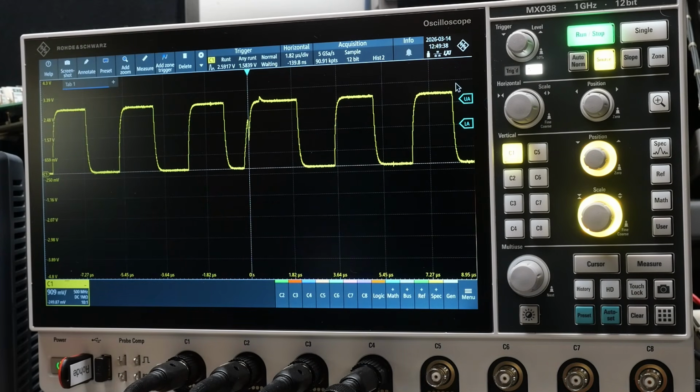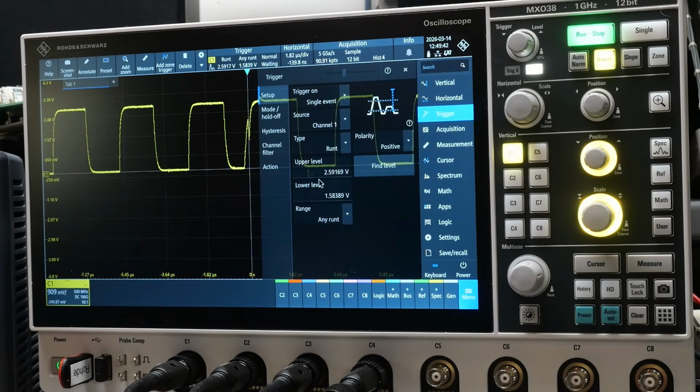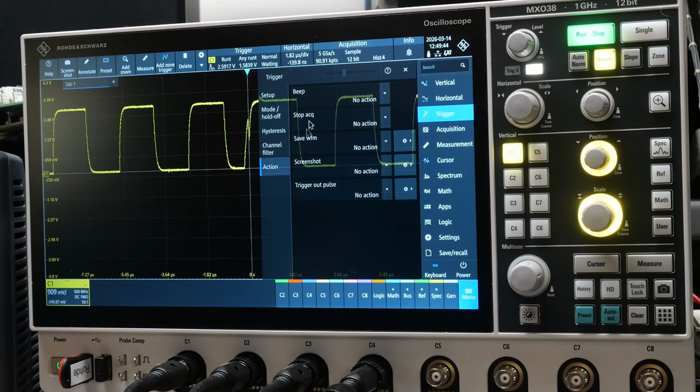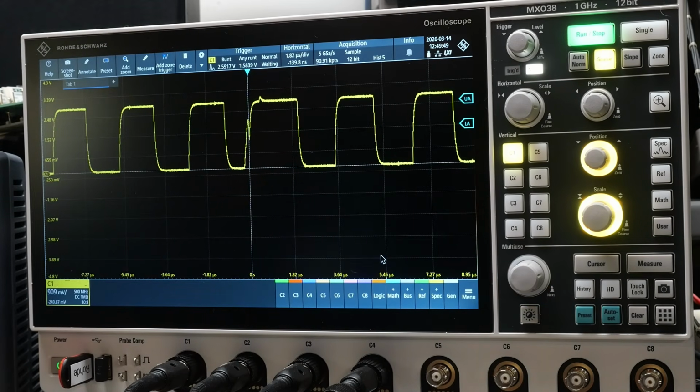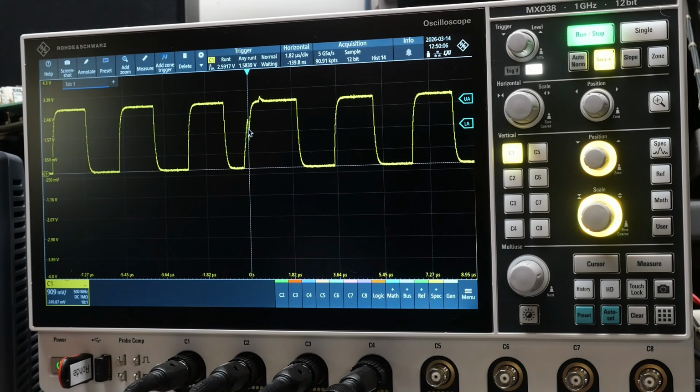So I saw one. I saw that flicker. I just happened to look and I saw the trigger light flash. So sometimes you can't see the trigger light flash. So what you'll do is you'll say, okay, let's beep if it actually catches something. Oh, there you go. So sometimes the display will stay the same, so you didn't know you got one. So having this beep to catch the runt pulses is great. So that's another way to do it, is runt pulses.